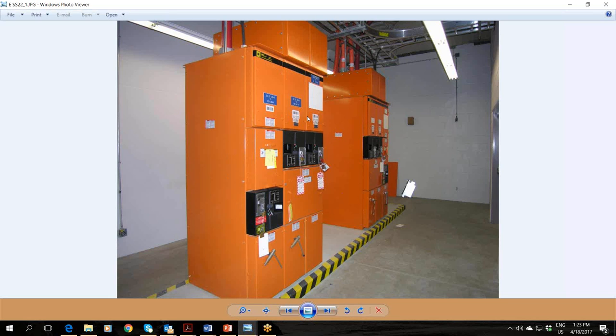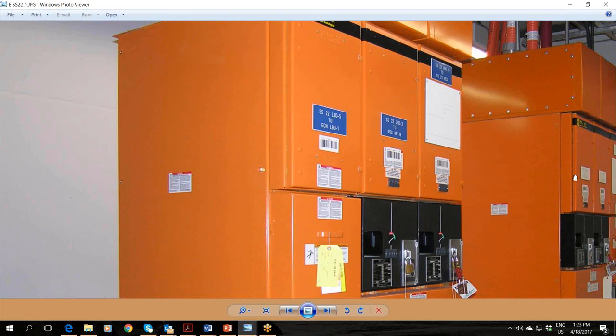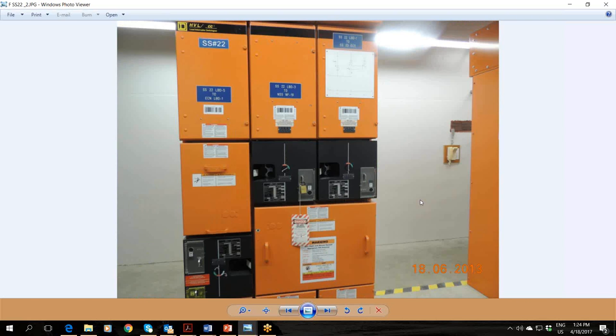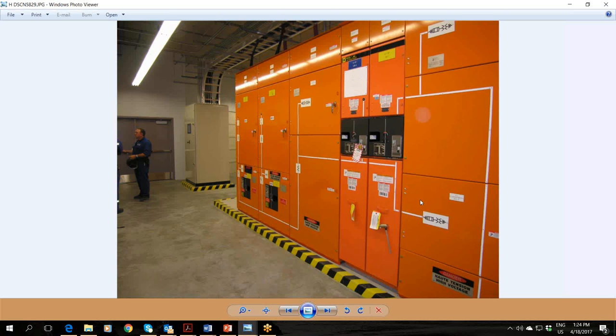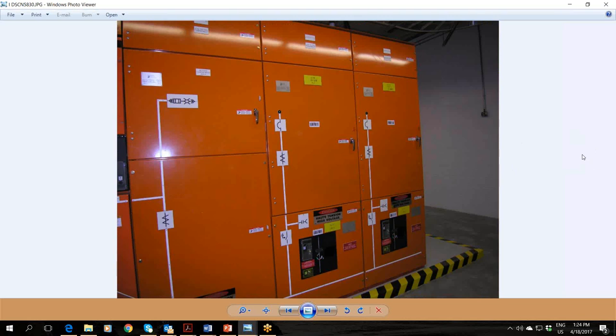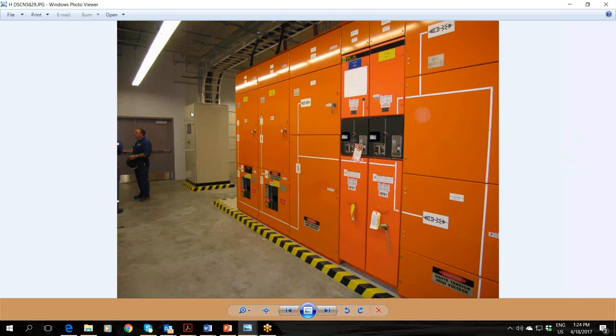Some photos for that. This is again a sectionalizer associated with that building. It happens to be sectionalizer 22. There's the blue, there's the white. Just a couple more photos of that from the front. This is the 15 kV switchgear with those fixed mounted breakers inside of that building. And again, the style of equipment is very similar. We've always had, as far as I know, primary metering. So we meter at the 15 kV level, at 13.8 nominally, and we bill based on that primary metering. That requires some larger metering sections, which you're seeing here in that new equipment.